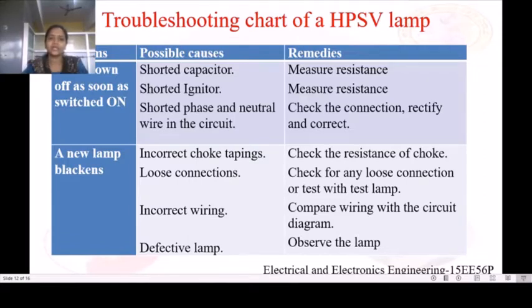Next, shorted igniter. For this also, we need to measure the resistance of the igniter. If the resistance of the igniter is high, we say that it is in good condition. It will be in terms of mega ohms. If it is low, we say that the igniter is not in good condition. Next, shorted phase and neutral wire in the circuit. For this, we need to check the connection physically, and also we need to rectify and correct it.